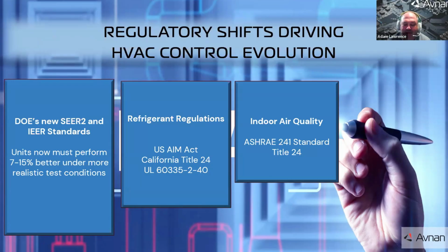Now let's talk about the key regulatory changes that are driving real change in HVAC control systems, what's coming, and what it means for all of us. First up, the Department of Energy's new SEER2 and IEER standards. These kicked in January 2023 and increased the bar for energy efficiency. Units must now perform 7 to 15% better under more realistic test conditions. To hit those targets, manufacturers have to move towards variable speed compressors, precise fan modulation, and smarter control loops. For us in controls, that means our systems need more diagnostic depth and tighter feedback control.